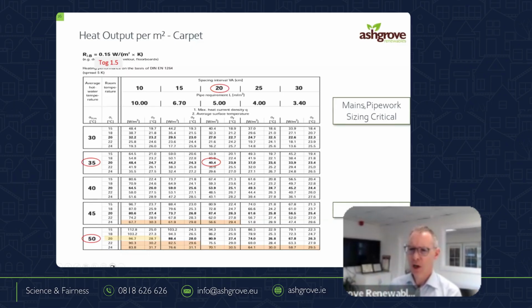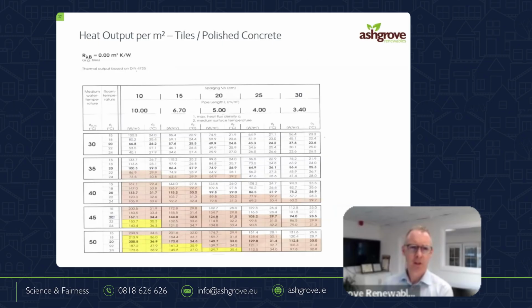that happens. Mains pipework is critical, obviously, should go without saying, but a properly designed underfloor heating system typically has a delta T of about 4 degrees, so the water going out and the water coming back have only 4 degrees difference, maybe 5. It can operate at a higher delta T, but it's harder to balance it. But of course, when I'm only dumping 4 Kelvin for each litre I'm dropping into your house, typically that's 10 or 11 or whatever it is with oil or gas boilers, my pipework now has to get 2.5 times bigger. I need to shift 2.5 times the amount of water. My pipework has to get bigger. That doesn't happen, right? Anyway, so conversely, if I do have the car showroom and I don't have carpet, I have tiles here or polished concrete or whatever it is, I can get at 4-inch centers, I can get 100 watts, right, at 35 degrees.